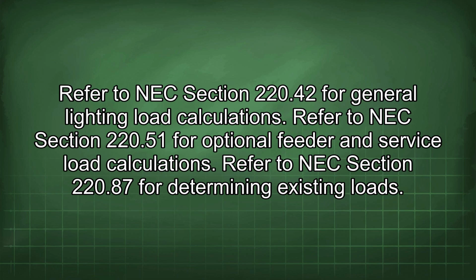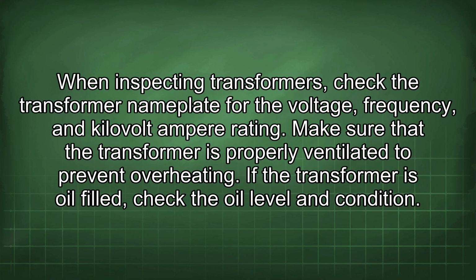Refer to NEC section 220.42 for general lighting load calculation. Refer to NEC section 220.51 for optional feeder and service load calculations. Refer to NEC section 220.87 for determining existing loads. When inspecting transformers, check the transformer nameplate for the voltage, frequency, and kilovolt-ampere rating. Make sure that the transformer is properly ventilated to prevent overheating. If the transformer is oil-filled, check the oil level and condition.